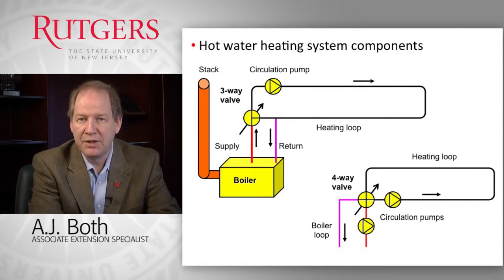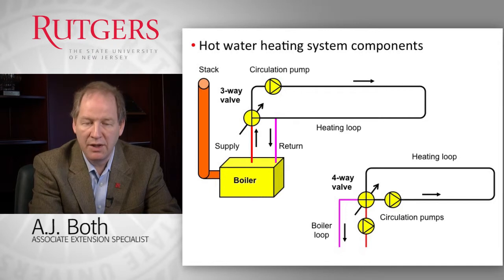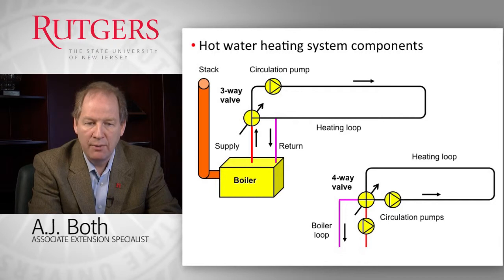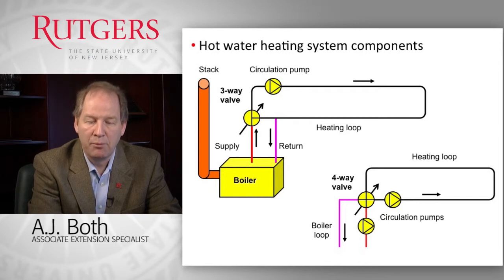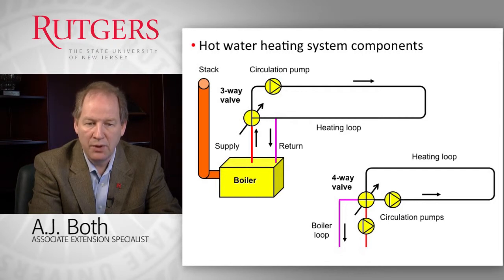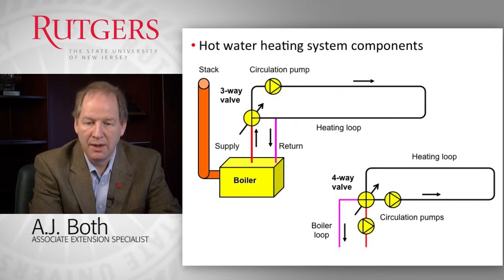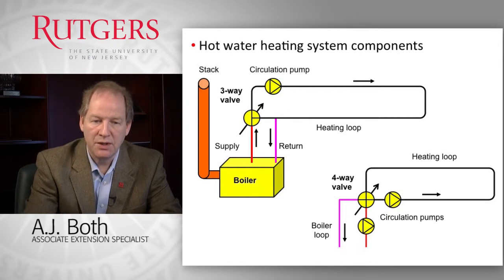Components of hot water heating systems include the boiler, where you combust your fuel and heat the water. Then you need to distribute that water throughout your greenhouse using pumps and valves — sometimes three-way valves, sometimes four-way valves — to push water through the plumbing system to the locations where heat is needed. This slide shows simplistically two different designs for three-way versus four-way valve systems.